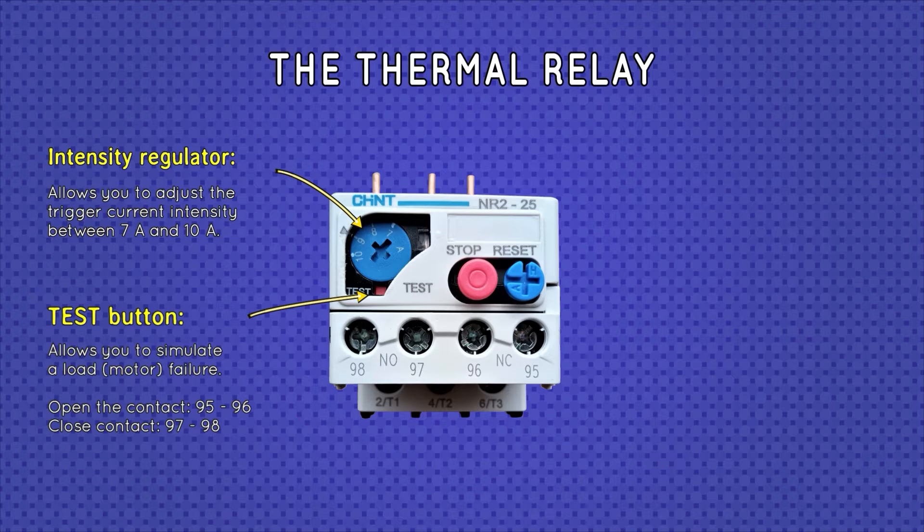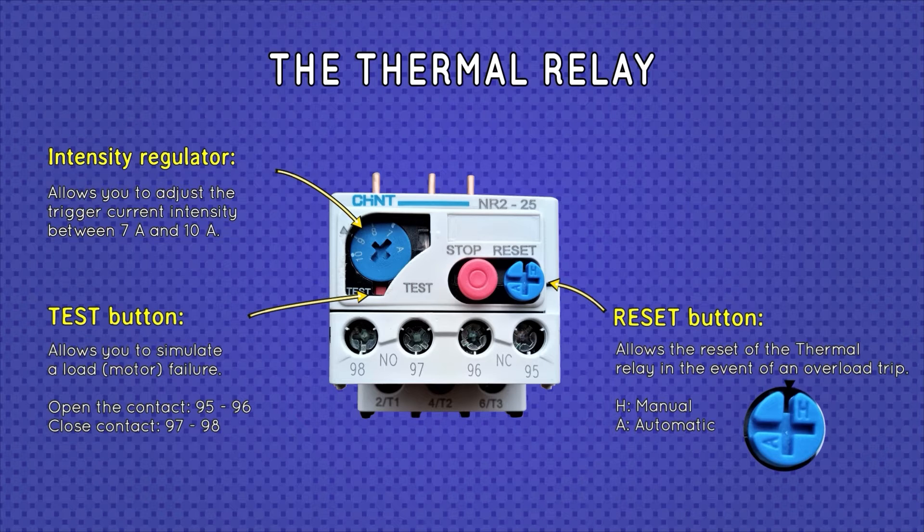The reset button allows the reset of the thermal relay in the event of a trip due to overload or having simulated a fault with the test button. The reset button can be found in manual mode, which means that we must press this button to reset its contacts, or automatic mode, which without the need to press anything after a while automatically resets its auxiliary contacts.